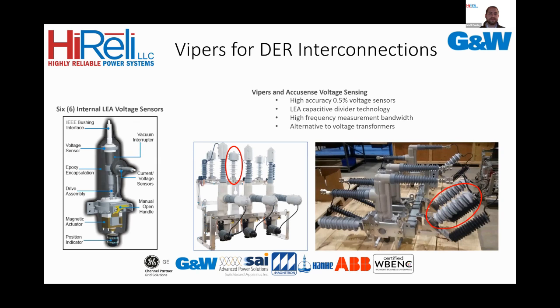So first, looking at Vipers for DER interconnections into the utilities. We typically see these at the point of common coupling, Viper reclosers with 6 voltage sensors. On the left-hand side, you can see we have 6 internal low energy analog voltage sensors that are molded within the module. These are capacitive, not resistive, so you have your isolation between primary and secondary. All cables and connections are molded within the module, so you don't have to worry about any squirrels or anything attacking the cables.